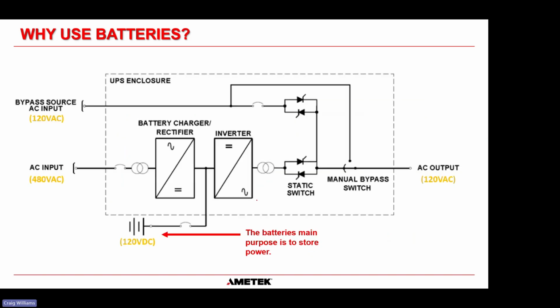And for a UPS, the battery's main purpose is to store power. So once again, we have 480 volts going into a battery charger rectifier. That is connected to this DC bus. And that DC bus is keeping the batteries charged, okay? And the battery does act as a kind of buffer for any brownouts or any poor AC that's going in here. But then the inverter takes this DC and converts it back into pure AC. So the main purpose of the battery is to store power, but it does have some buffering capabilities for anomalies in the AC input supply.